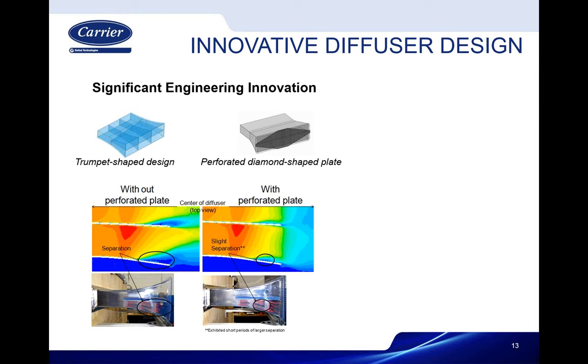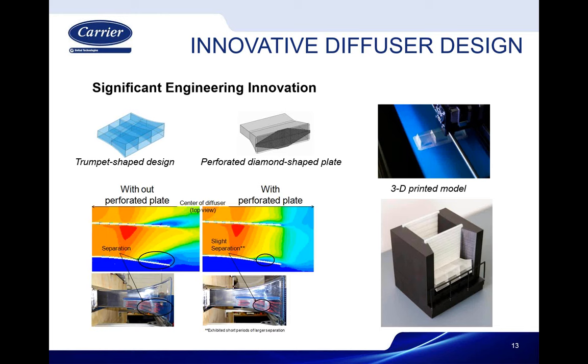We came up with an innovative design, putting a perforated plate across the areas that had the highest velocities. So we basically said, let's try to impede the center throat of the diffuser and the other portions where we're seeing the largest amount of flow, to convince the air to spread out more and give us an entry velocity into the chamber that's low enough that we're not going to be banging into the walls on the other side.